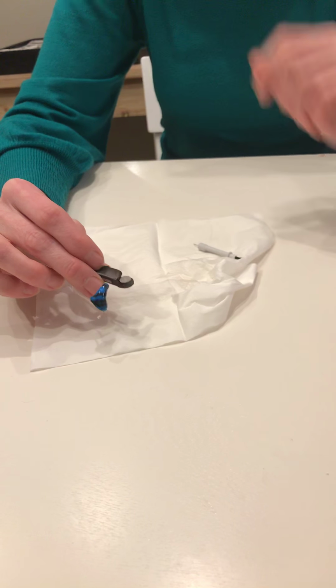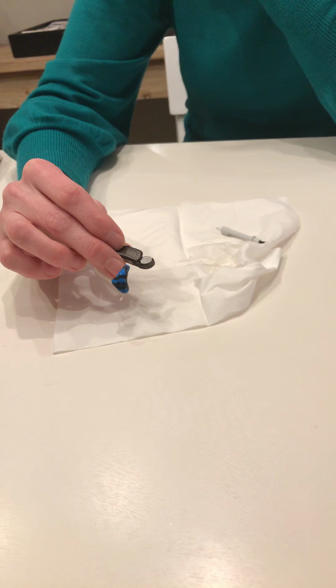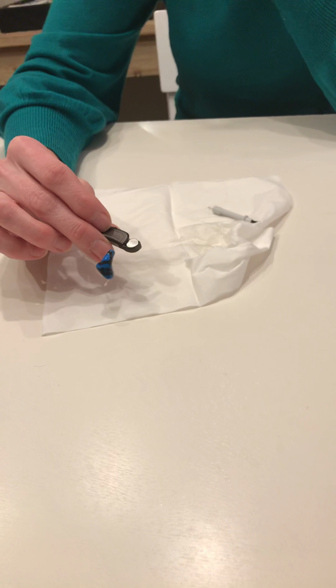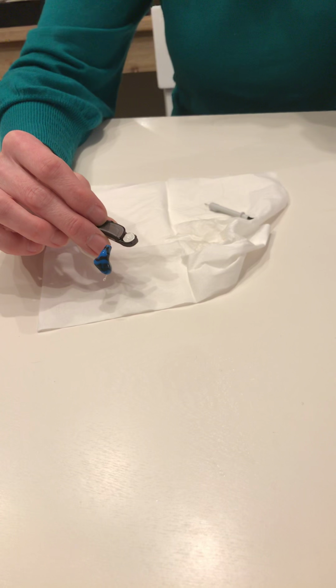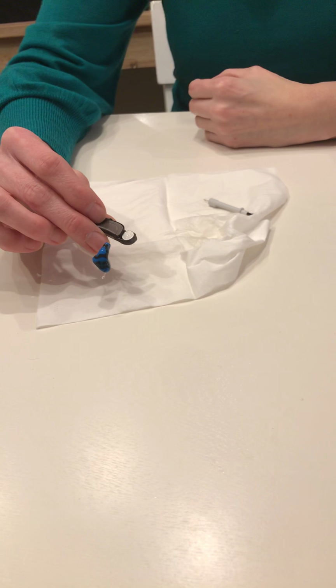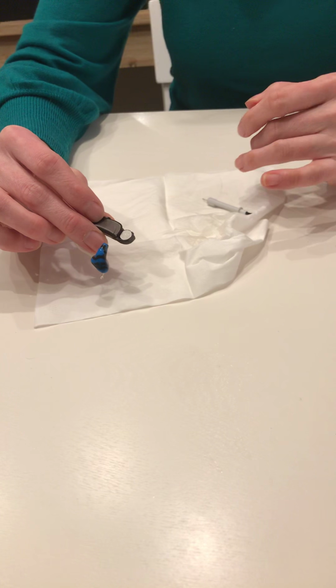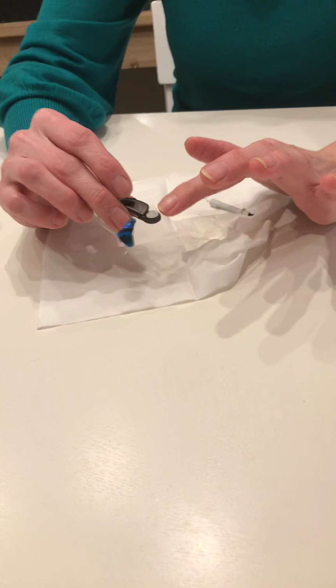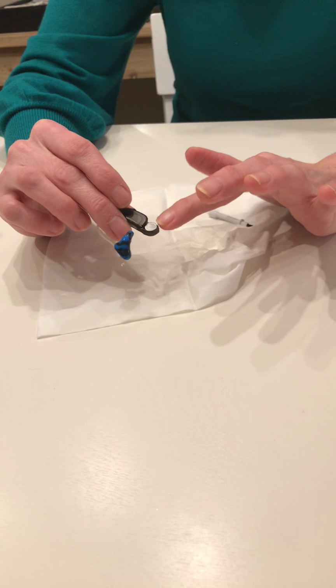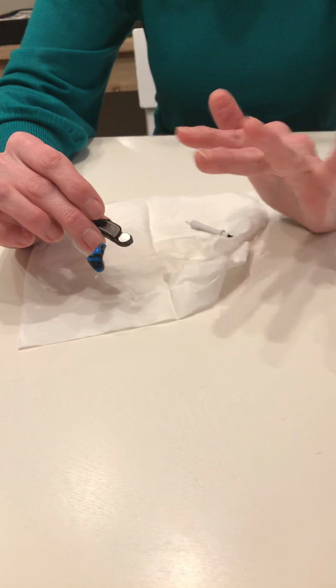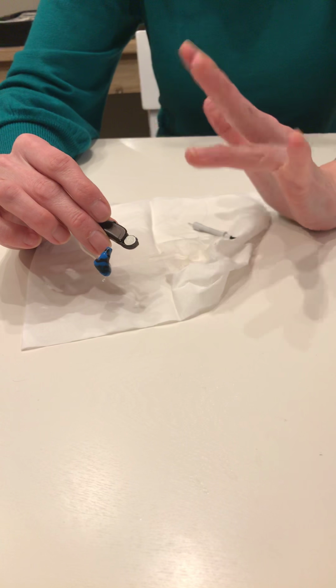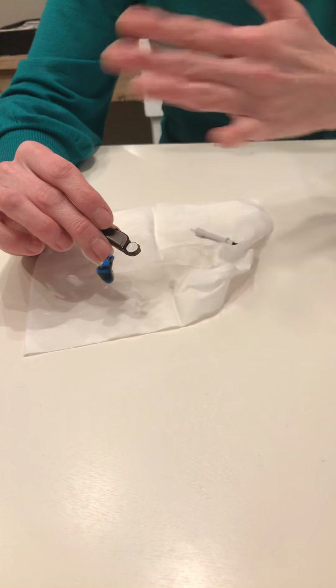The battery is going to last about 10 to 14 days, and if I were you, I would go ahead and just make a mark on the calendar and then change the battery every 14 days. If for some reason it dies sooner, she will know because she'll hear a brief beeping sound for about 30 minutes intermittently, and then the hearing aid will just die completely. There's very little downtime on a battery. It's either working or not.